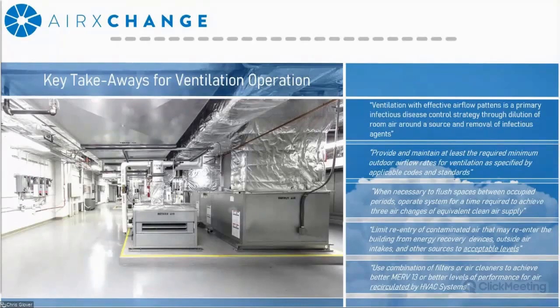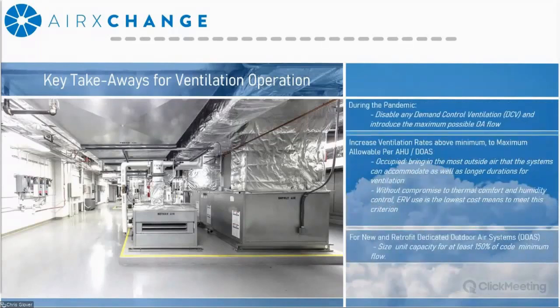Use a combination of filters or air cleaners to achieve MERV 13 or better levels of performance for recirculated air. I highlighted recirculated here because it's important to understand how recirculated air is required for achieving this step, and I'm going to talk about that again in a couple of slides. Okay, so disable any demand-controlled ventilation. Carbon dioxide is often used as a reference gas to determine occupancy, and its purpose is to minimize outside air based upon occupancy. Since most educational spaces are being used or will be used at part occupancy at this point, you don't want the control algorithm to inadvertently lower the ventilation rate.